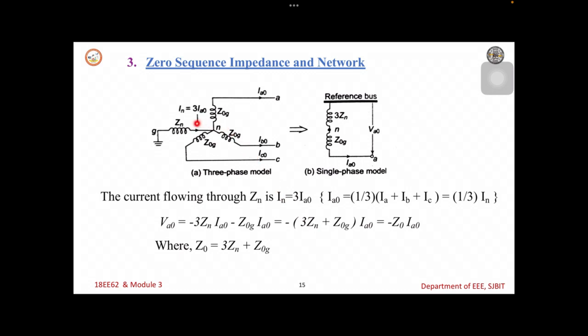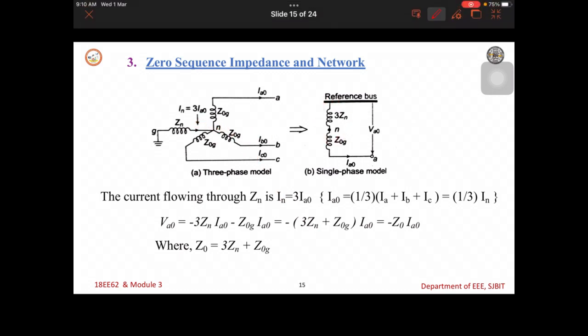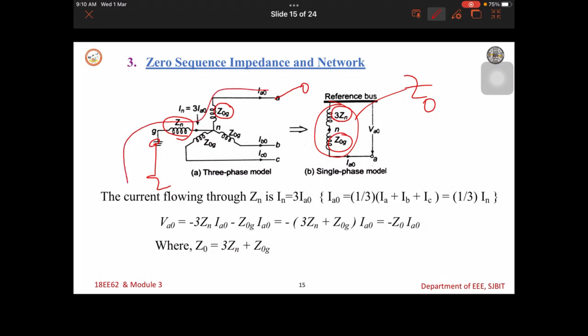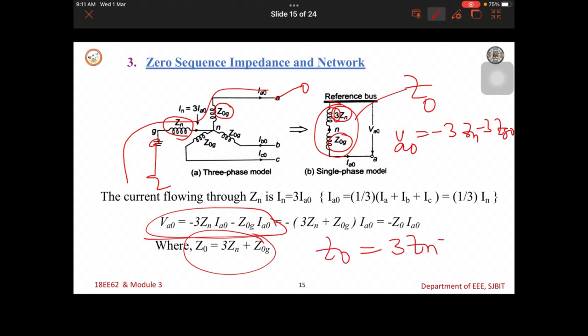Similarly, we can write the zero sequence impedance and network. This is the zero sequence impedance. I will write this put together. This put together is the zero sequence impedance. This zero sequence impedance has two terms: one is Zg0 and three times Zn. Why? Because from neutral to ground, neutral to phase A, if you see the total impedance, that is Zg0 and Zn, and this path is carrying a current of three times Ia0. Therefore, 3 is considered here, Ia0 is here. So that voltage Va0 is equal to minus 3 times Zn minus Zg0 here. So this is the formula for the terminal voltage Va0. Here the zero sequence impedance is the sum of three times Zn plus Zg0.